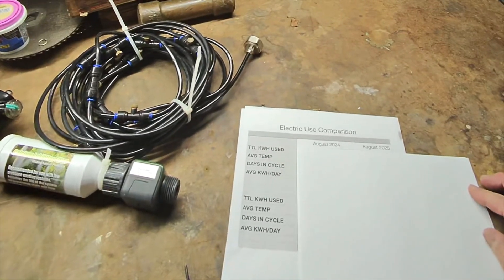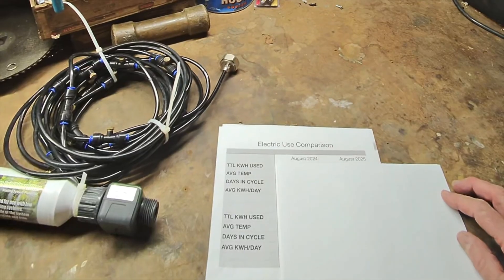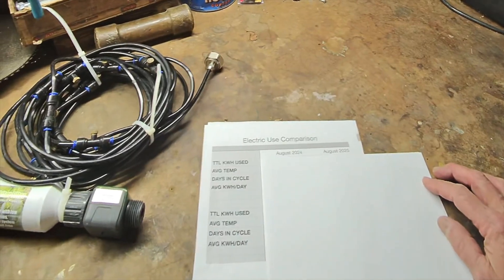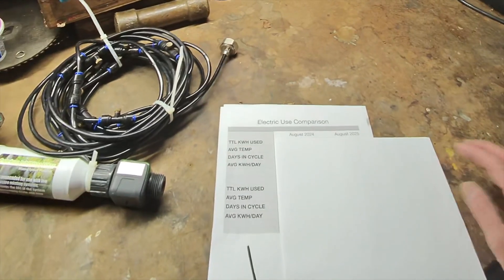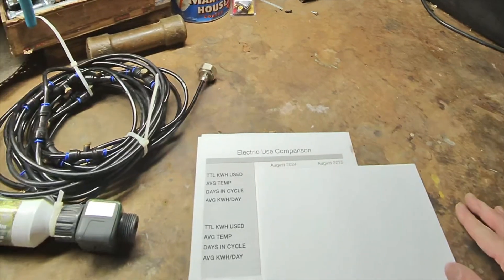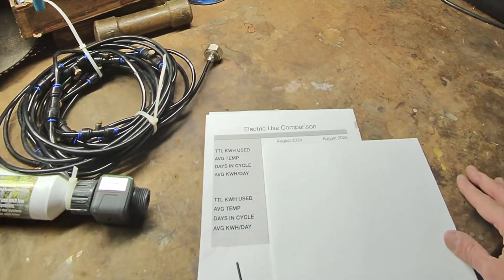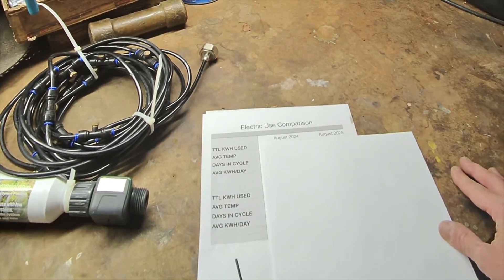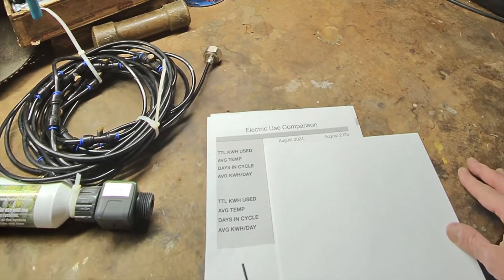All right, here we are back in the shop and it is time to compare the actual numbers. You know, as you may recall, when we were setting this up, we were testing. And we would take a look at the power draw without the misting system on and the power draw with the misting system on and compare the numbers. And it looked like we were getting about an eight to 10% reduction in power draw with the misting system on. So that gave us some hope.